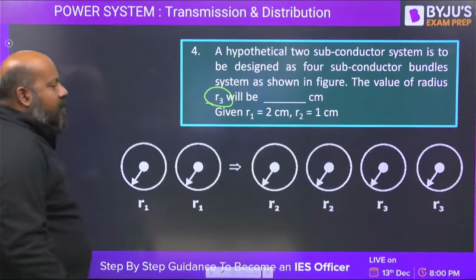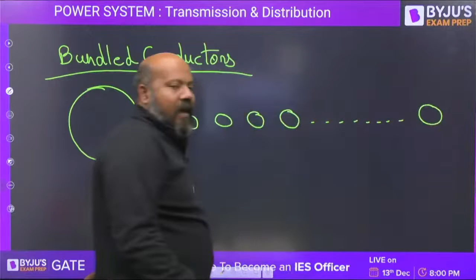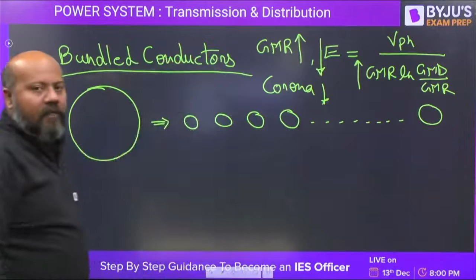Now please understand. What is the basic idea about bundled conductors? The moment you hear bundled conductors, what is the basic idea? A single conductor is divided into a number of small radius subconductors. Why is it done? It is done to basically increase the GMR. Because if GMR is increased, the electric field stress at the surface of the conductor, which is V phase over GMR ln GMD upon GMR, reduces. This is logarithmic, so GMR increasing means electric field stress reduces, so corona reduces. So we use bundle conductors basically to reduce the corona or the electric field stress at the surface of the conductor.